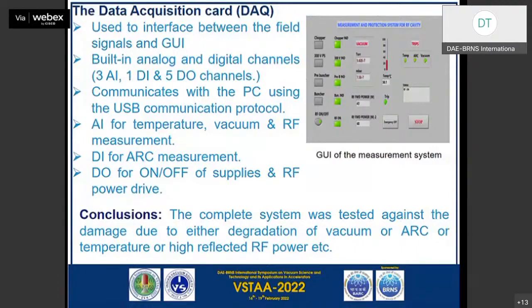Shiju, just one query: you capture different physical phenomena through the data acquisition system - temperature, vacuum, and RF signals. These don't all change at the same rate, so how do you fix the sampling frequency given these signals have different rates of change? As for the data acquisition system, the sampling rate is 48 kilo samples per second, and we are taking temperature, vacuum, and RF signals continuously.